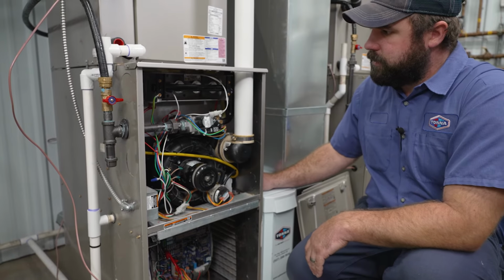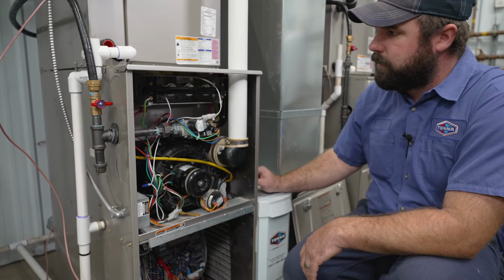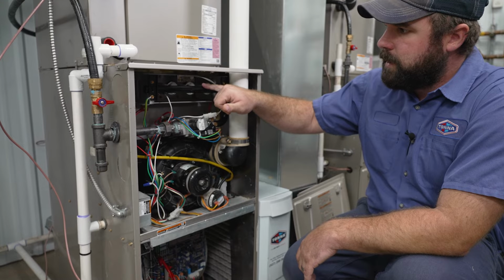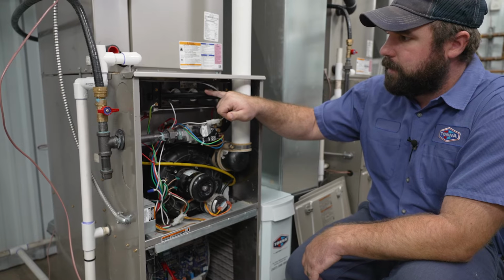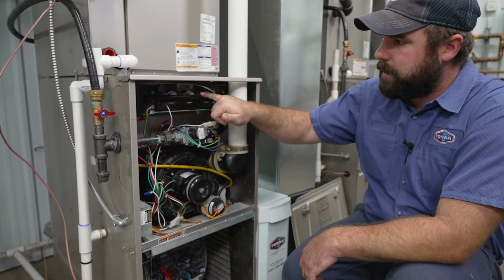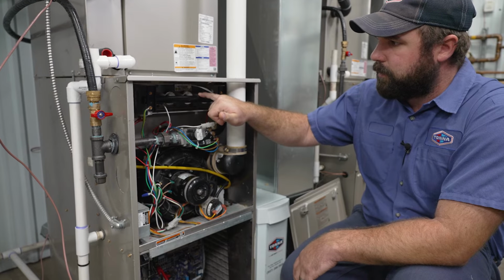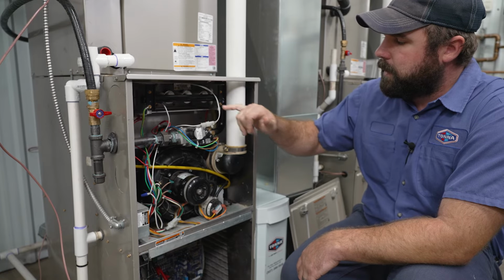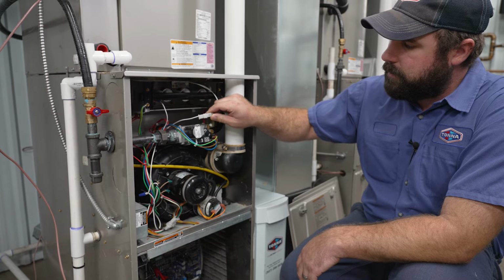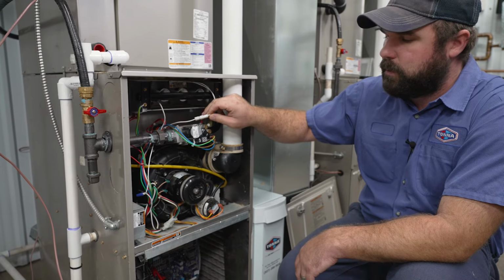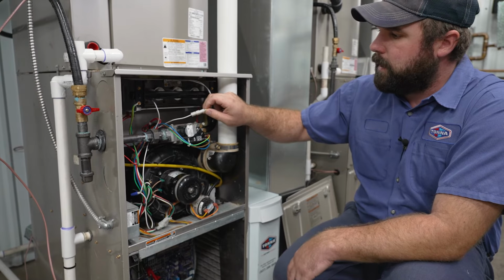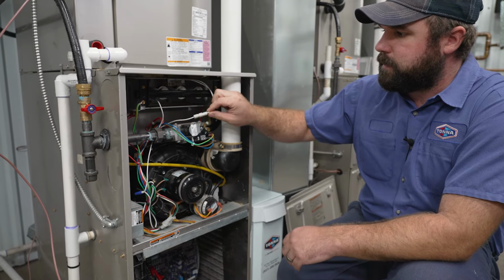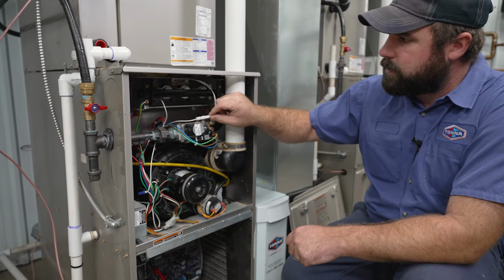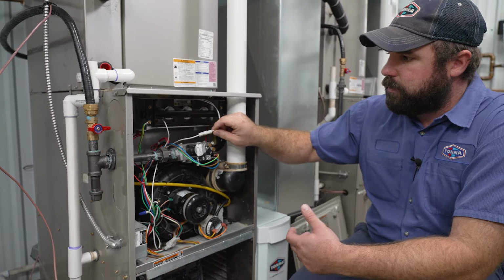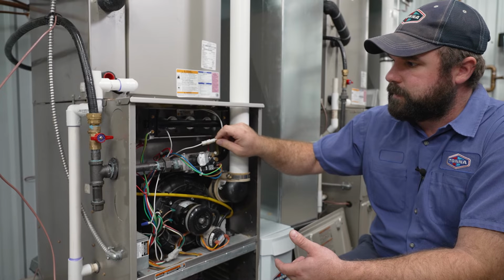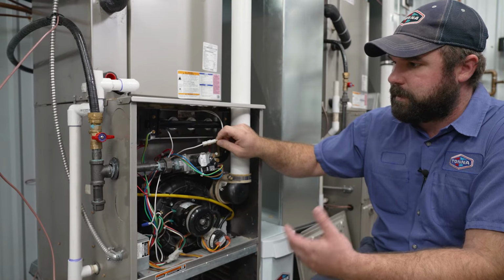And then we visually check the furnace from top to bottom, checking out your burners up here, making sure they're free and clear, without much rust or soot. Some of them, if they're not burning properly, will show soot. Then we will check your igniter, ohm that out, make sure it's reading properly, to ensure that it doesn't break down as well.